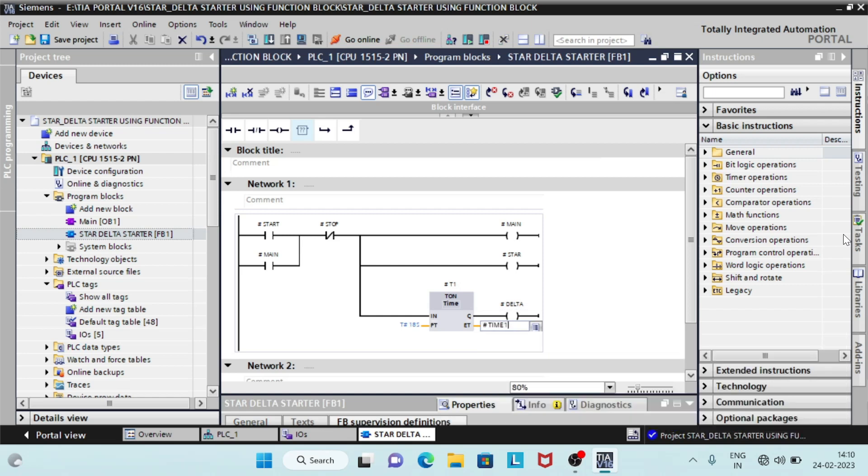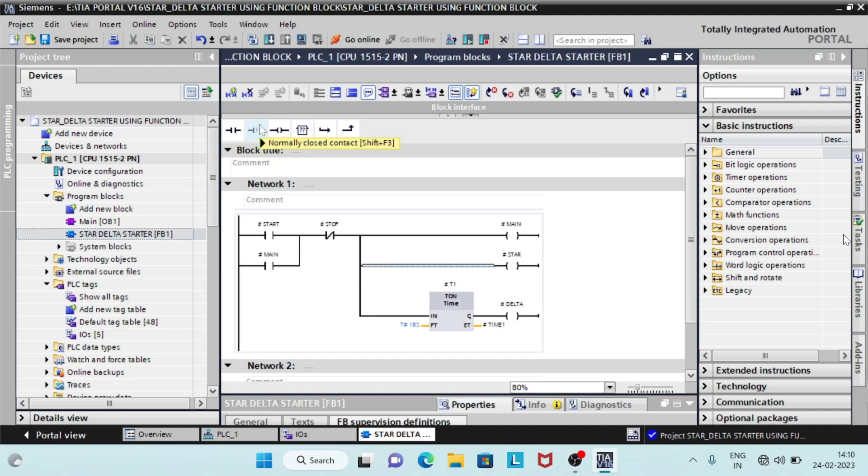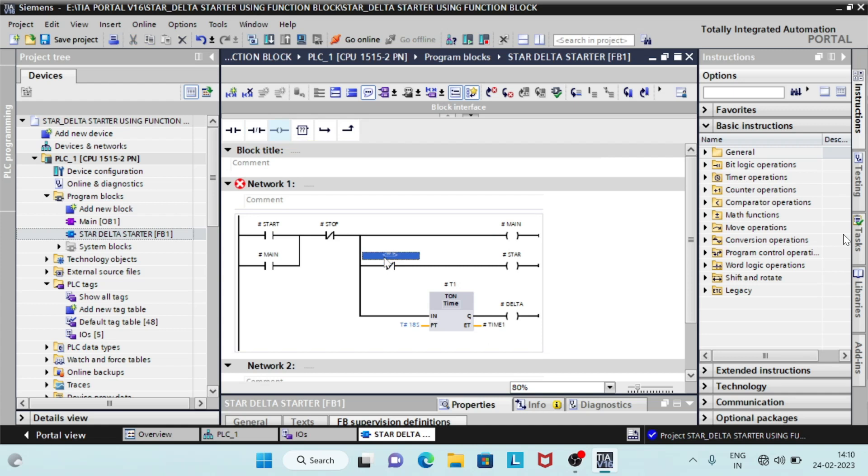When delta coil is energized, the star coil must be de-energized. For this, we will use delta coil NC contact to de-energize the star coil.